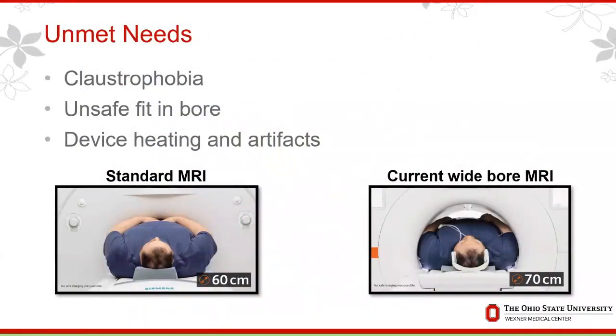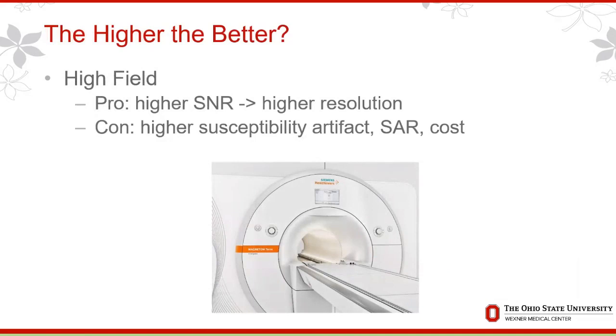Other access barriers here in the U.S. that could limit cardiovascular care — especially in the obesity epidemic — include claustrophobia, the inability to fit safely in the bore, and device heating and artifacts. Historically, it was felt that higher magnetic field strength scanners would produce higher quality images through higher signal-to-noise ratio, representing currency towards higher resolution. Unfortunately, some cons for higher field strength included higher susceptibility artifacts, higher SAR and subsequently heating, and increased cost of manufacturing the device and supporting infrastructure.